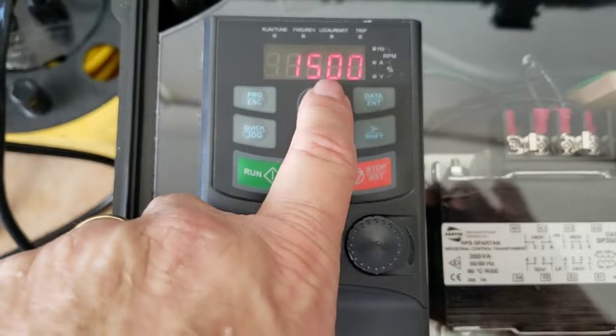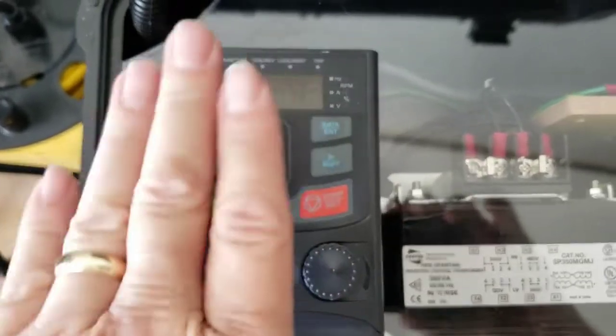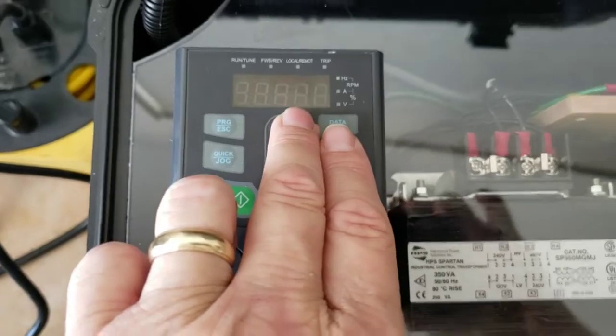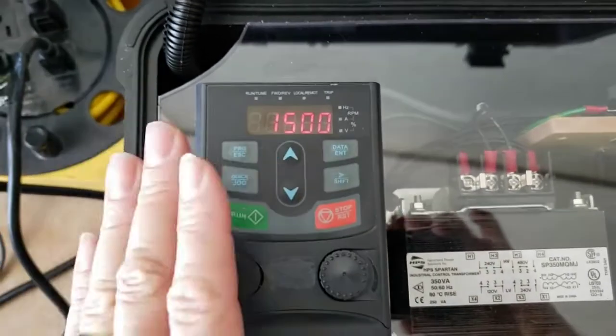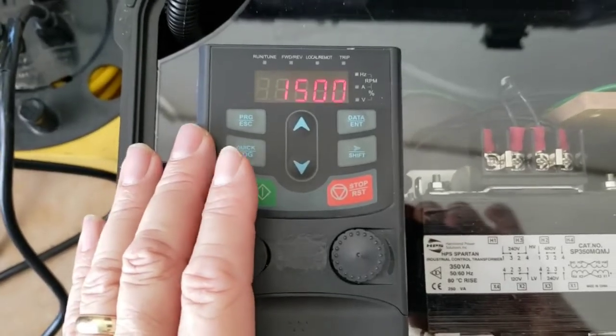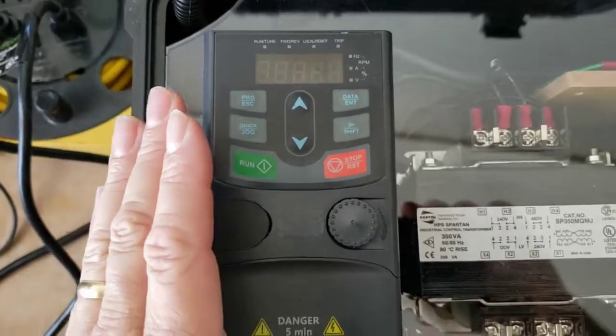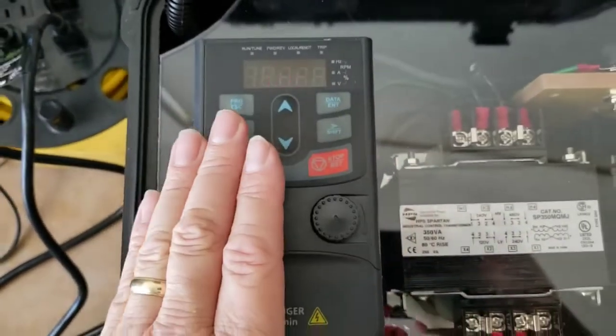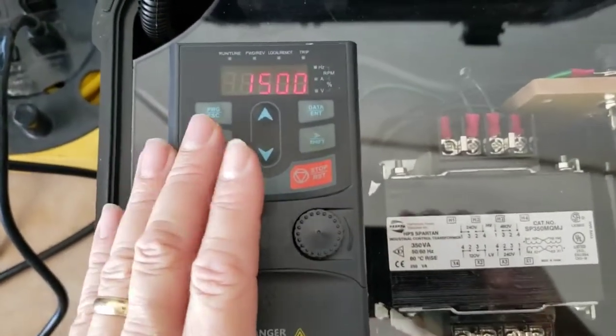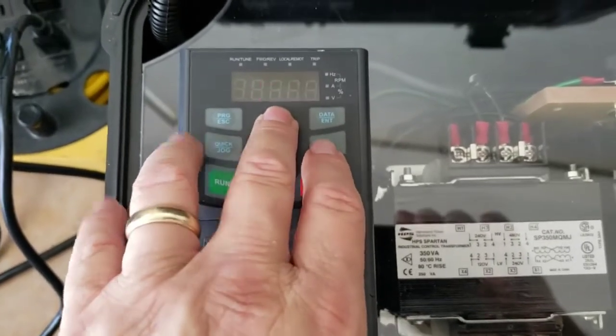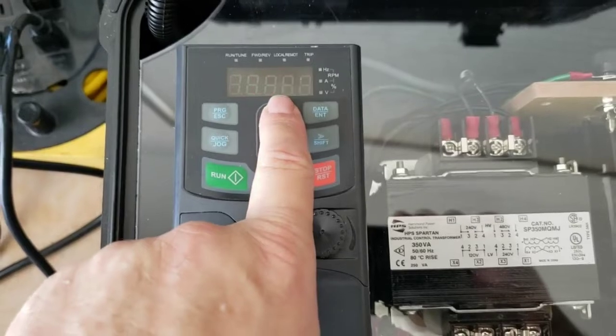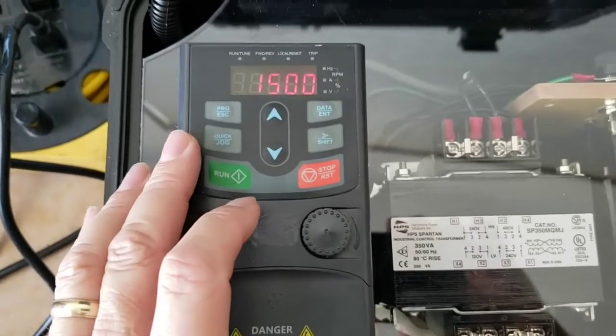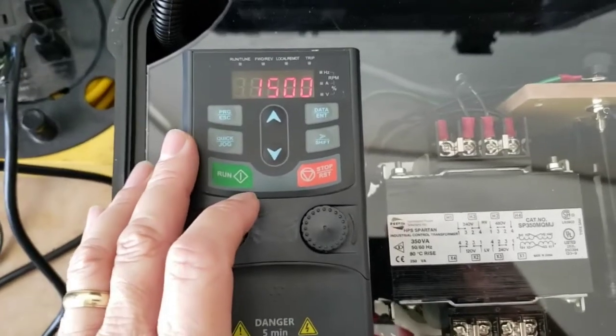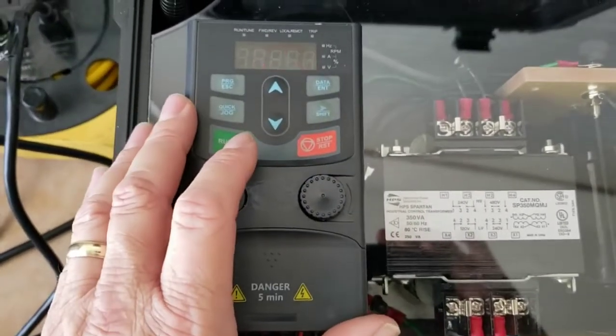When I do that, the next startup for one cycle, it's going to do a sweep all the way from 1500 hertz. What I've currently got this one tuned at is it'll go from 1500 hertz up to 9500 hertz, and it'll find the resonant frequency for the cell you're hooked up to. If you've got a known cell, like one of our OWS cells, with this system it would go up to roughly 8000 hertz. If it doesn't follow that same pattern and hit the peak at those frequencies, you can also detect a bad one. And also, as it sweeps past various frequencies, certain resonant frequencies may trigger an arc inside if there's a compromised enamel on the electrode.